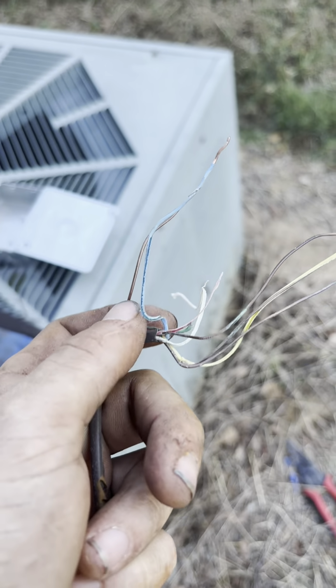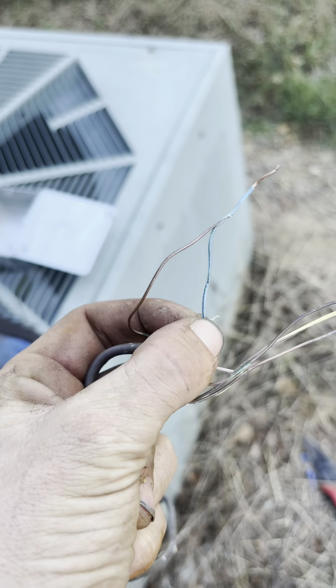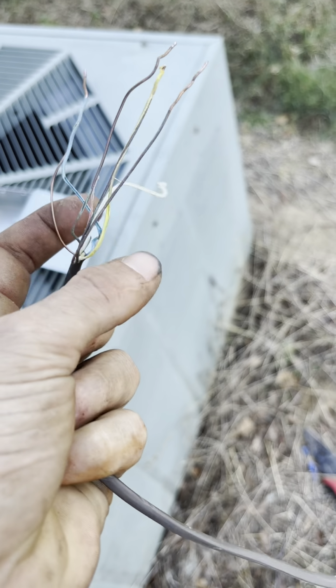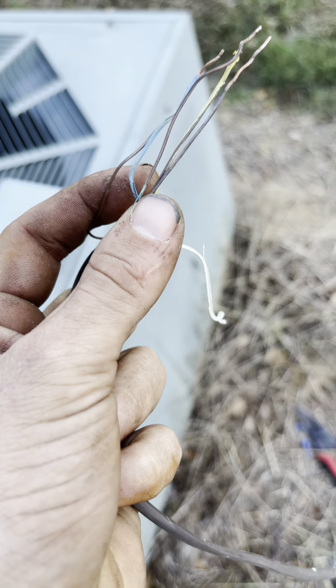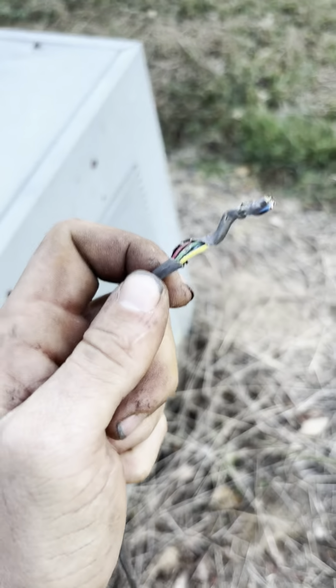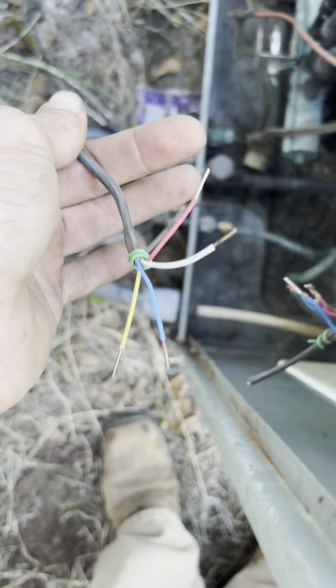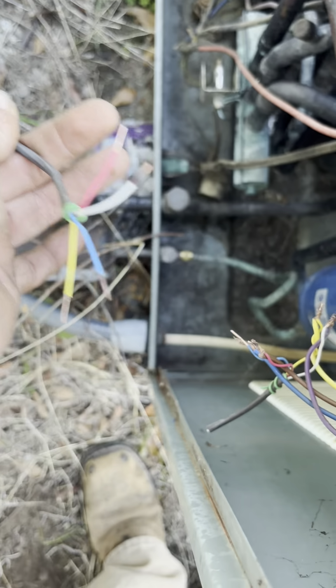So then I came out here to the outdoor unit and I saw this. You see that? That's the insulation coming off the wire. That's all bare wires touching each other. And I also found this spot right here. Looks like it's been chewed by a dog or something. I don't know if y'all can see that, where it's nicked. And that causes all of these wires to cross and blow things like transformers.